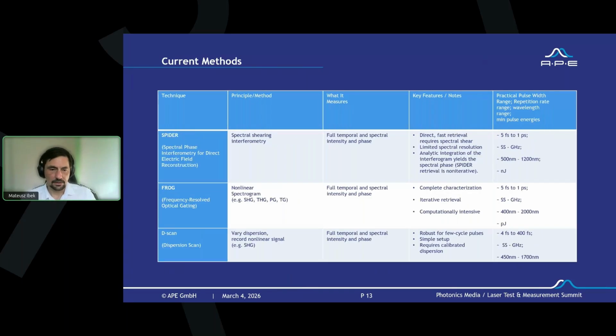The more sophisticated methods that give us also the spectrum, spectral shape, and phase and temporal shape are SPIDER, FROG, and D-scan. Starting with SPIDER, which stands for spectral phase interferometry for direct electric field reconstruction. It is a spectral shearing interferometry, which combines two pulses. One is dispersed through material. They are interfered with each other. It is a direct measurement of the electric field, and it gives us full temporal and spectral intensity and phase. Since it's direct, the retrieval is fast.